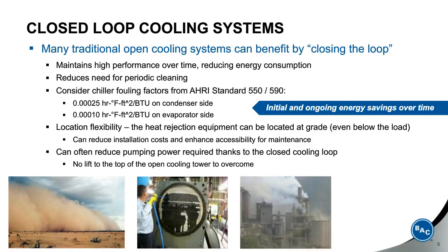Now, many traditional open cooling systems can benefit by closing the loop. This helps you to maintain high performance over time, reducing energy consumption. It also reduces the need for periodic cleaning. Now, you can consider the chiller fouling factors from AHRI standard 550/590. The standard fouling factor for the rating on the condenser side is 0.00025. Yet on the closed evaporator side, which is the chilled water side, it is 0.0001. This makes about a 1.2% difference in energy efficiency, but if you would close the condenser side, you would save energy, and it would be an initial and ongoing energy savings over time.